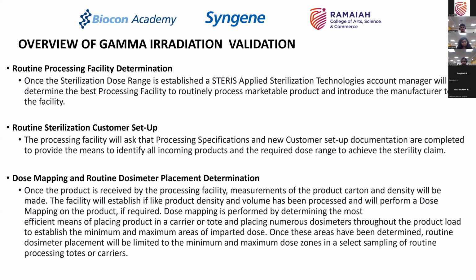So once you have now given the documentation, you have the data, you have the window in which you are going to do the dosages. Now what next? When you go to a processing facility, if they already have done a similar load pattern or number of product cartons with the density. So here it goes by the volume, the size of the carton converted into a volume and weight. If they have already done that kind of a process earlier, then they would probably know where to place the dosimeters during the routine process itself.